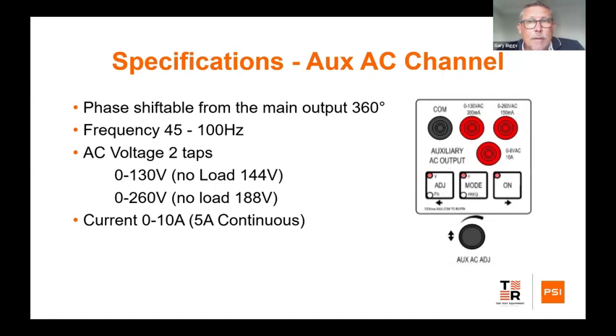We have an auxiliary AC channel in addition to the main output channel. Now the main output channel, if you feed it with 50 hertz, it will give you 50 hertz out, and if you feed it with 60 hertz, which you guys would do, it will give you 60 hertz out. With our unit, we have a second channel, which is totally controlled. It's an electronic channel. So we have the ability to shift the phase from the main output from 0 to 360 degrees. We can control the frequency from 45 to 100 hertz. And we have two voltage taps there: a 0 to 130 volts, and a 0 to 260 volts.